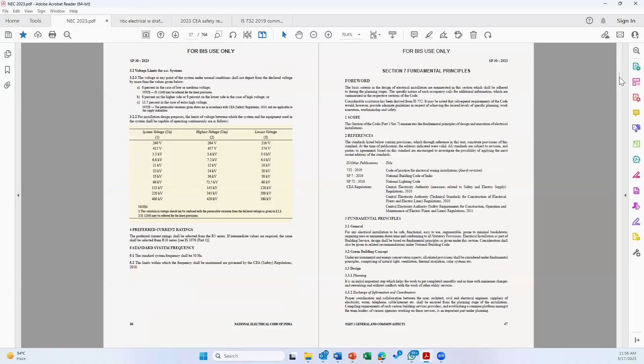Actually, this was the very old concept. Probably this concept came from historic documents of the 1950s, 1960s. Whereas in the NEC, what I'm showing, we have updated this information to a large extent. Now, a lot of people know that earthing doesn't mean earth electrode. Earthing means how efficiently you are making the equipotential bonding, which was written in all the standards and regulations for decades, but there was a picture missing. Now in the NEC, what you are seeing in the picture is an illustration of earthing and protective conductors, just to explain how earthing has to be made.